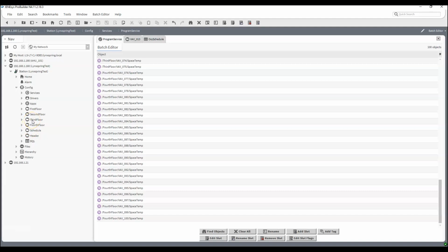Those are the couple, those right there, being able to create a link. So it needs to be Baja link. To add a history, it's going to be the history and do whatever history extension you want. Now, the thing you're not going to be able to do just through program services alone is adding alarm extensions. The reason being is that adding alarm extensions requires a multi-function program.